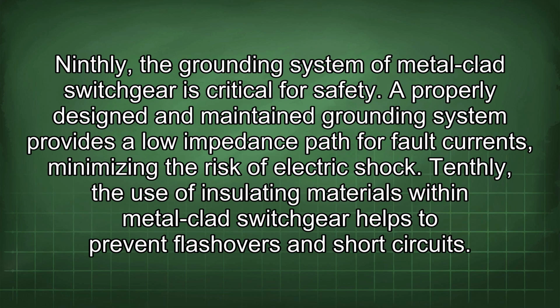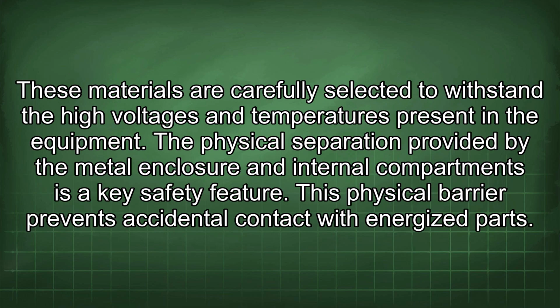Ninthly, the grounding system of metal-clad switchgear is critical for safety. A properly designed and maintained grounding system provides a low impedance path for fault currents, minimizing the risk of electric shock. Tenthly, the use of insulating materials within metal-clad switchgear helps to prevent flashovers and short circuits. These materials are carefully selected to withstand the high voltages and temperatures present in the equipment.